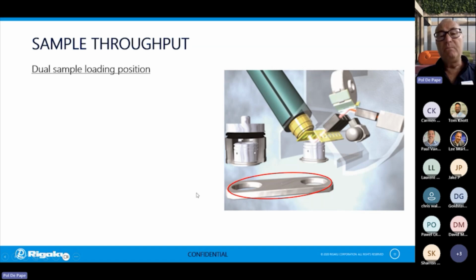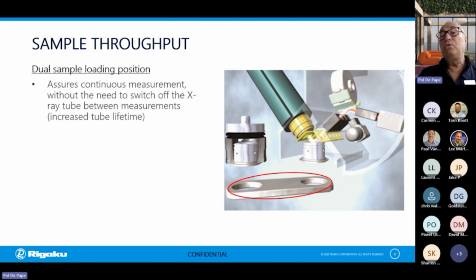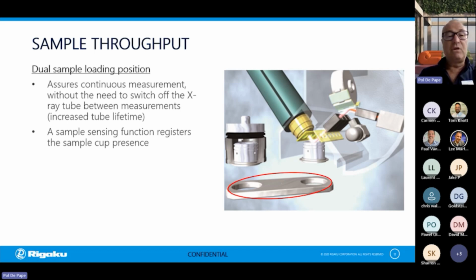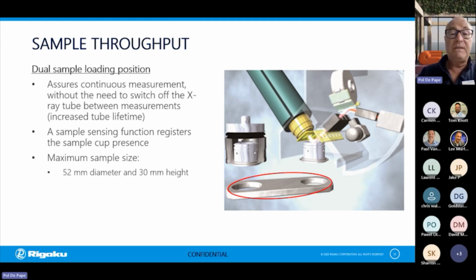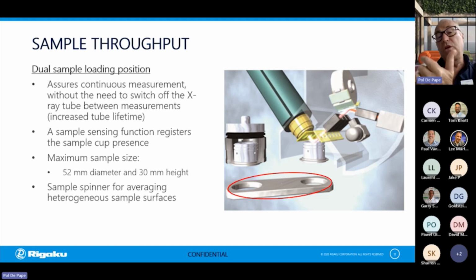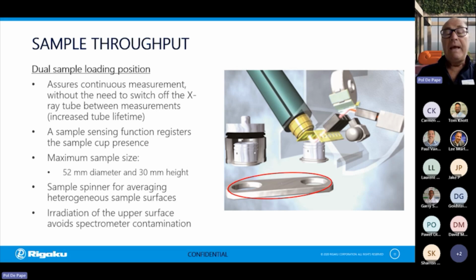So we have a dual vacuum pump system. This means that we use one vacuum pump for the spectrometer chamber and the other vacuum pump for the pre-vacuum chamber. So we have our X-ray tube switched on at any time, and this is of course very important to increase the tube lifetime. And we also have, of course, a sample sensing function. So in this dual loading position tool, we have sensors that detect if there is a sample cup present or not. Sample cups can contain samples up to 52 millimeter in diameter and up to 30 millimeter in height. And we also have a sample spinner that takes care of averaging eventually heterogeneous sample surfaces. And once again, we have the tube above, so we have the irradiation of the upper surface, which avoids contamination of the spectrometer.